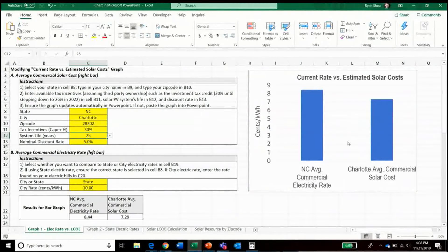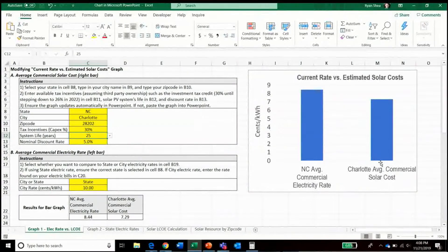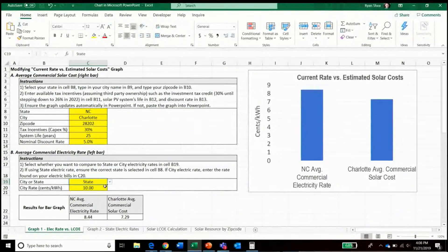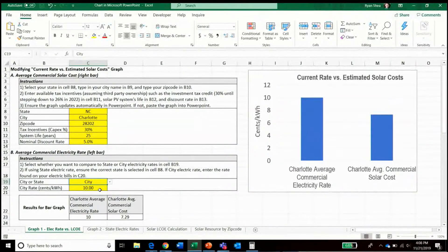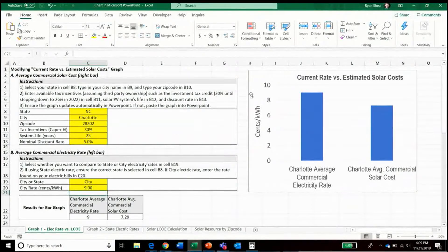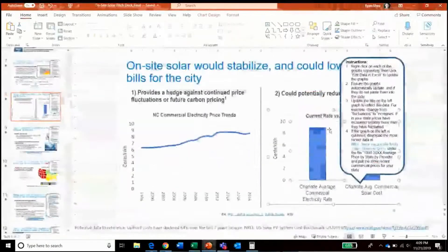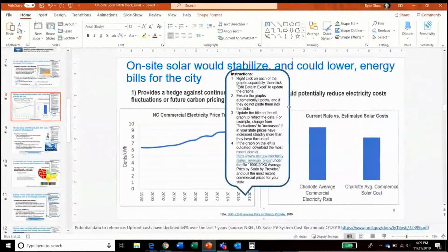Then decide whether to keep the defaults of a 30% tax incentive, 25-year system life, and nominal discount rate of 5%. What will happen is the graph on the right will calculate the commercial solar cost as the levelized cost of electricity. For the bar on the left, decide whether to use the city or state electricity rate — in this case we could assume the city rate of around $0.09 per kilowatt hour. Then confirm that the graph updates accordingly in the presentation, which it does.